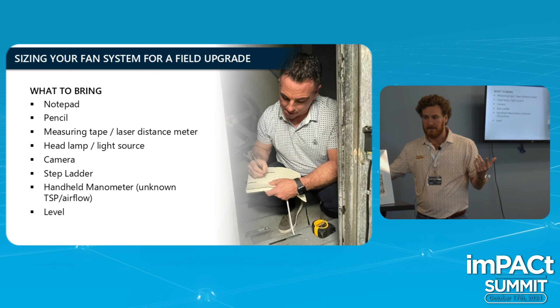If you select a system where the MOCP is larger than what's existing, you'll need to change out the infrastructure—maybe a new breaker or different size conductor—which adds cost and can cause trouble on a project. So if that's a concern, make sure you're matching the MOCP and pick the selection with the lowest power consumption. That's one of the things you really want to check on a job, and sometimes that information will be on the schedule, but other times it won't.